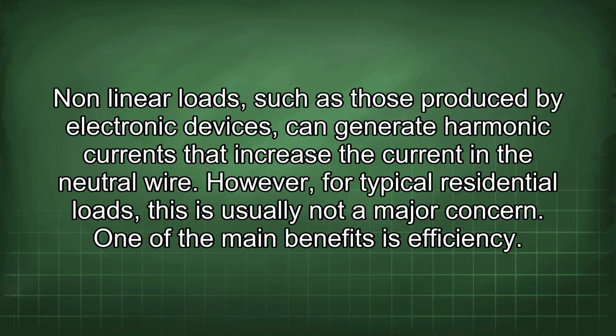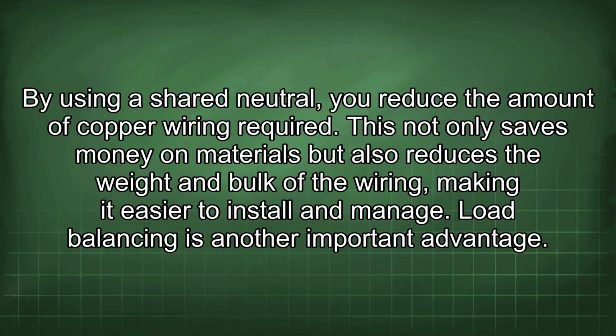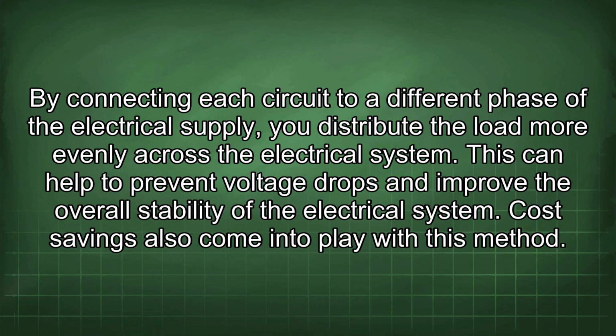One of the main benefits is efficiency. By using a shared neutral, you reduce the amount of copper wiring required. This not only saves money on materials, but also reduces the weight and bulk of the wiring, making it easier to install and manage. Load balancing is another important advantage. By connecting each circuit to a different phase of the electrical supply, you distribute the load more evenly across the electrical system. This can help to prevent voltage drops and improve the overall stability of the electrical system.